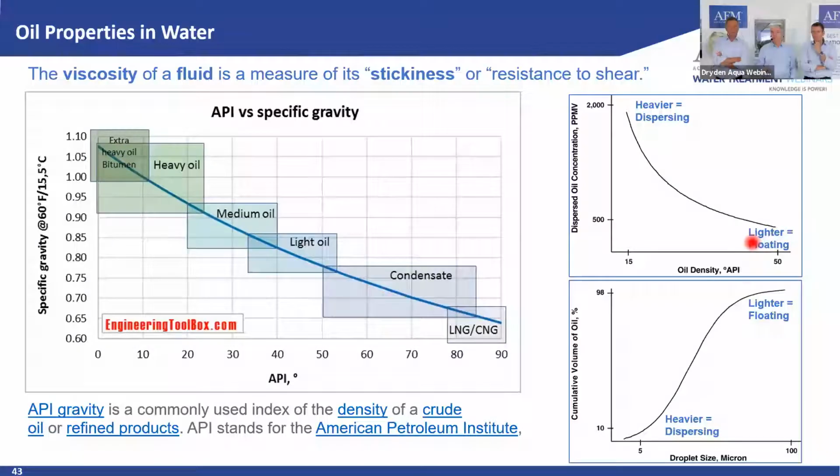That's very important for the removal process, because you have more heavier dispersed particles left at the end, very fine particles. That's the key, because the finer particles we remove with media filtration. The lighter ones, which are more volume, are already removed with different flotation processes before.